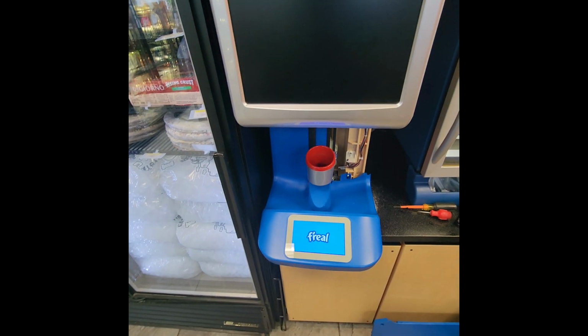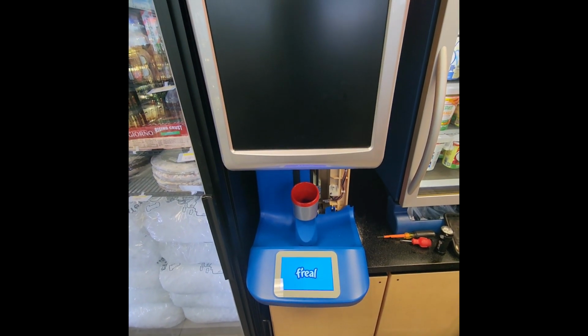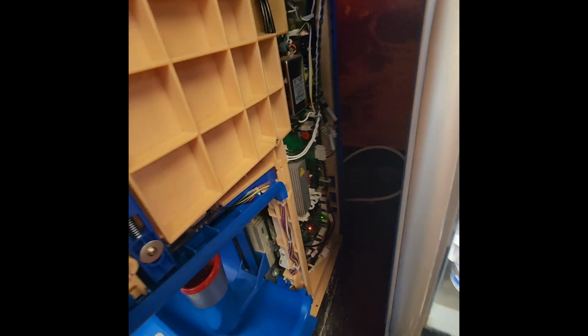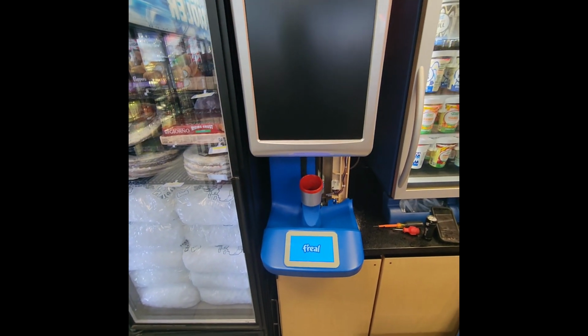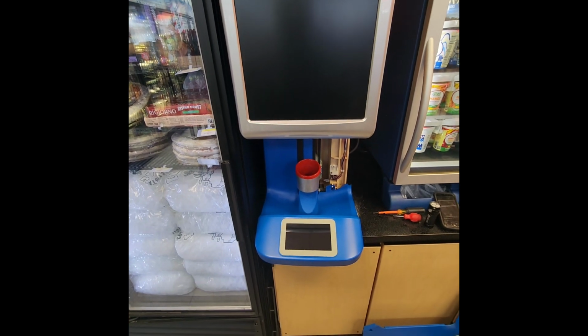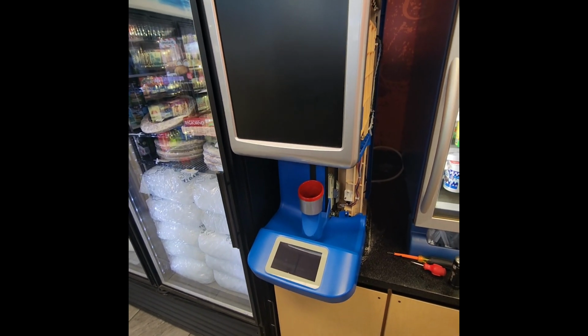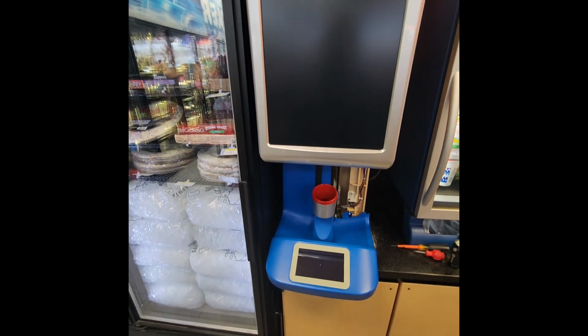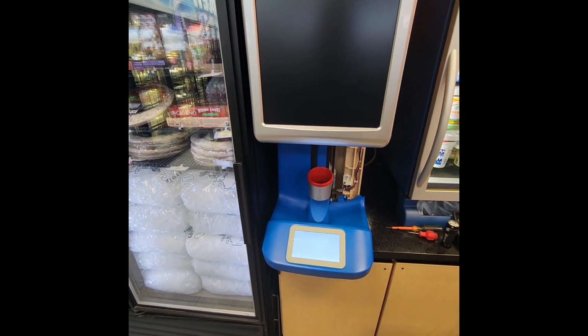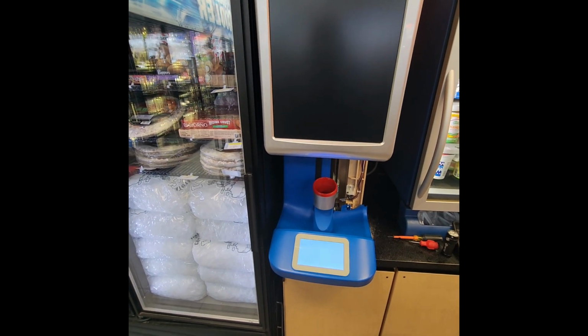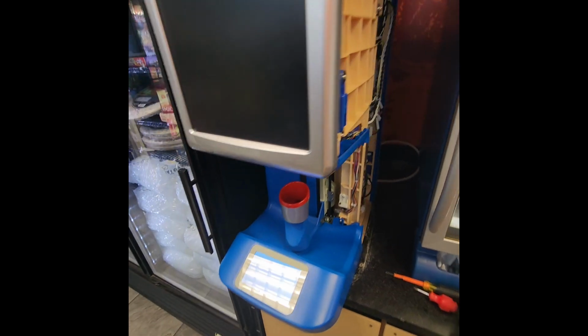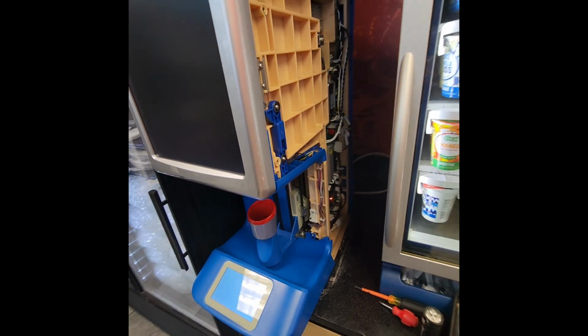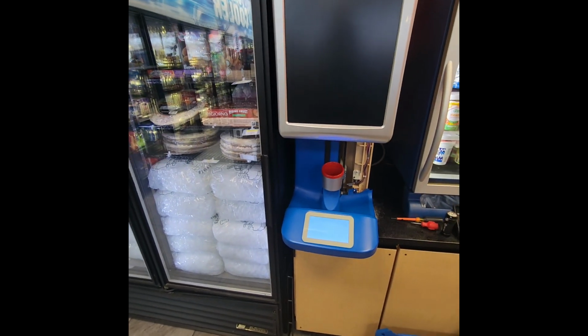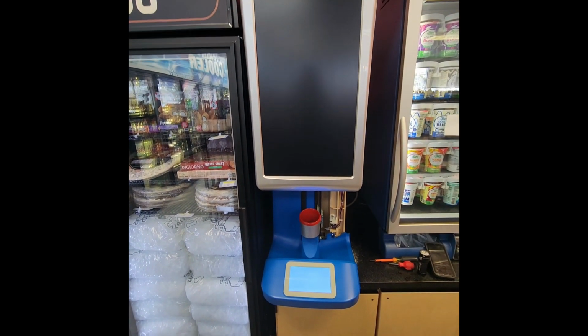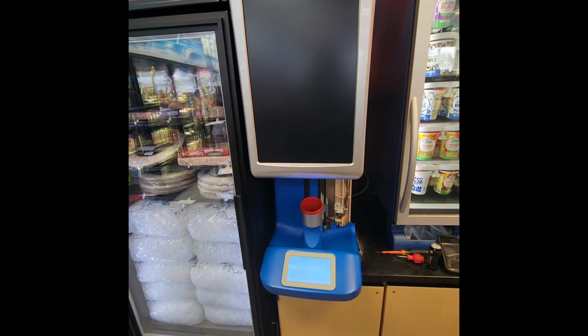So now I only have the pump motor connected, and I have the mix motor disconnected. This is just a way to troubleshoot and see what's going on. After this, I'll probably take some more continuity readings on that pump motor, because that's the one I'm suspecting is bad, but it could also be the mix motor too. So let's give it a second and see what it does.